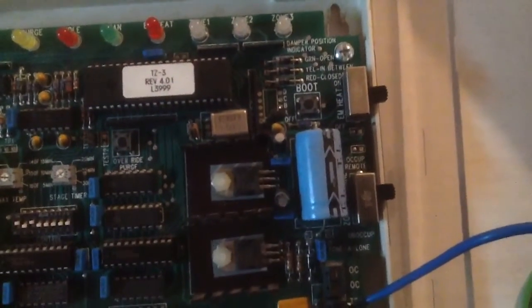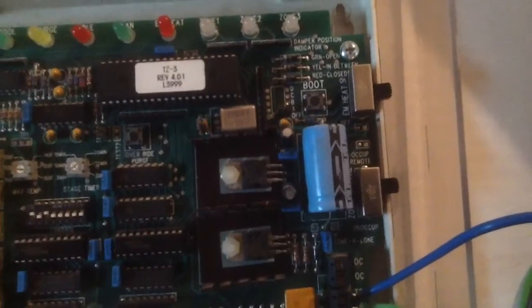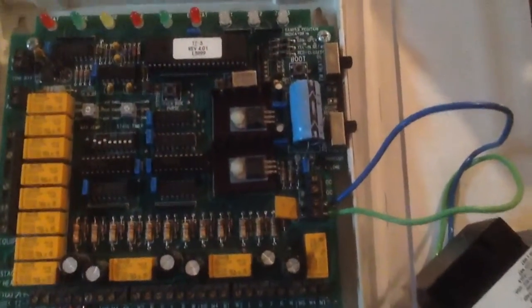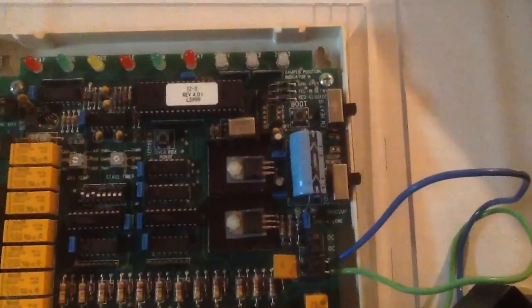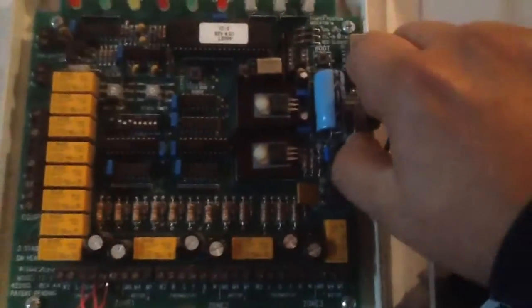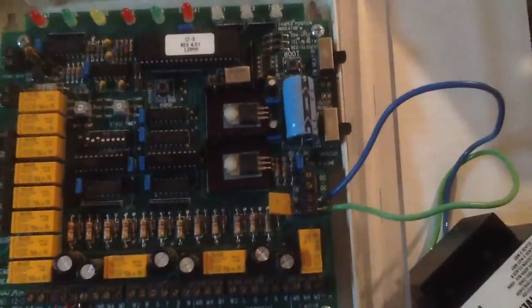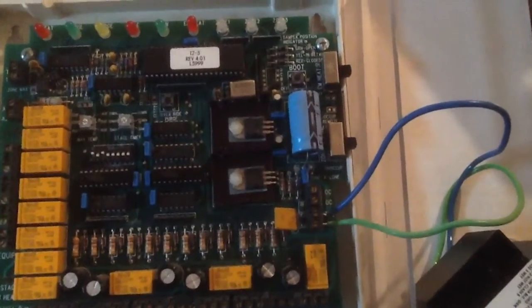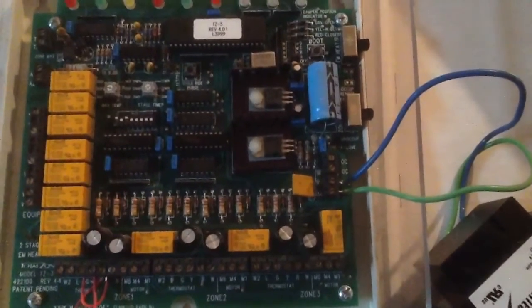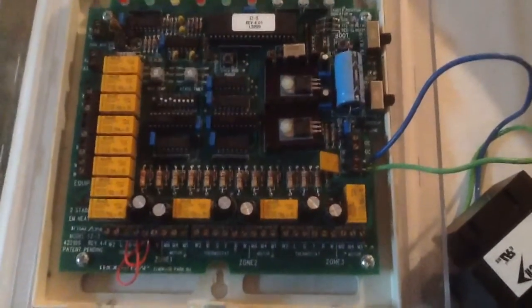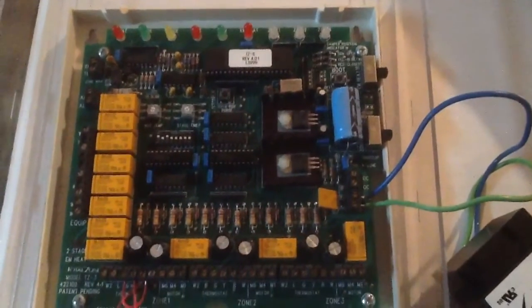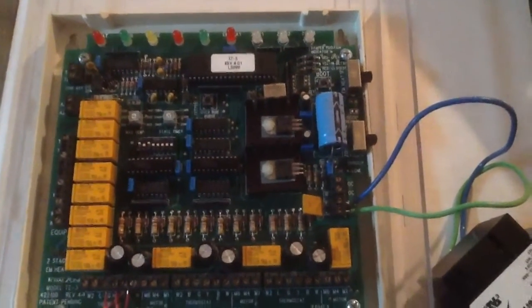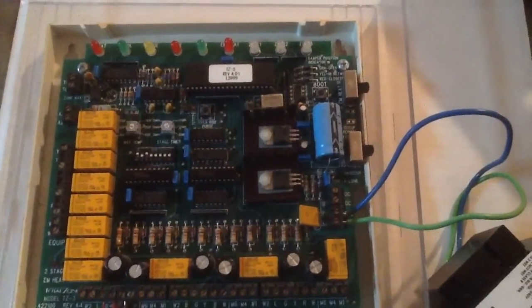Not all zone boards have these, but this zone board has a zone alone switch, which is right over here. Basically what that means is when it's engaged on the bottom here, like so, it'll actually bring on all three zones at the same time. So zone 1 typically will be the master zone, and if it's calling, it'll run all zones at the same time, heating or cooling.